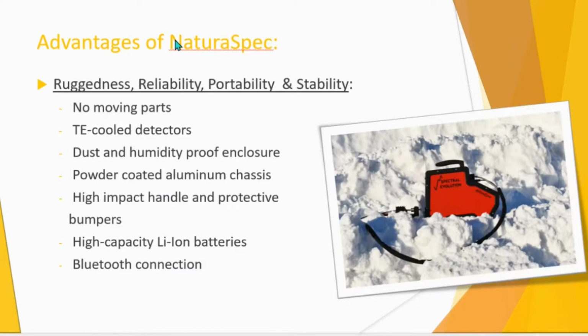To address the variability of temperatures in the field, our detectors are cooled. They're precisely cooled with thermoelectric modules to make sure that the detectors are going to operate within their sweet range, the optimum range for the detectors, and that the data will be repeatable from measurement to measurement. Our instrument comes in a metal enclosure, an aluminum enclosure, which is powder-coated. So it's a very strong enclosure to resist shock, vibration, scratches, and so on. Powder-coated to resist corrosion. And the optical path and the electronic path are in a dust and humidity-proof enclosure as well. So we can now operate in field environments without having the worries of the instrument failing because today it's too humid or too hot or too cold.